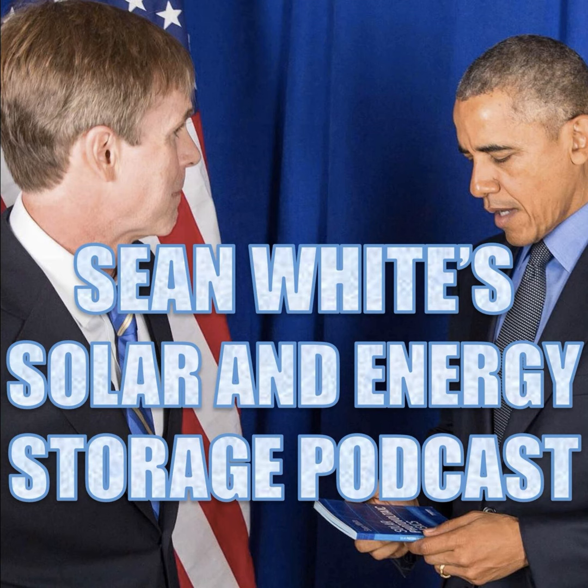The next thing about currents that we're looking at here is the KAIC. That's thousands of amps interrupting capacity. And that would be a rating that you would have for, say, a circuit breaker. So you might have a circuit breaker that could handle up to 10,000 amps. It might be a 20 amp circuit breaker, but if over 10,000 amps came rushing at it, it wouldn't be able to handle that much. So maybe you would have that on the load side of a main breaker that could handle more ampere interrupting capacity.